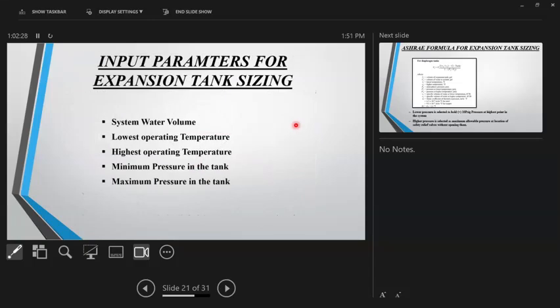Now for sizing these tanks, you must have sized these tanks at some point in your project life cycle. You simply require a system volume, which is the total volume in pipes, in heat exchangers and bends and whatnot. So, total system volume, and lowest operating temperature. What is the lowest operating temperature anticipated? For chilled water, it is the operating temperature. If it is 6-7 degrees centigrade, then that is the lowest operating temperature.